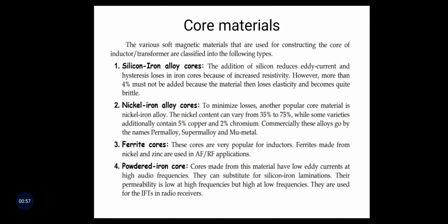First one, silicon iron alloy cores. The addition of silicon reduces eddy current and hysteresis losses in the iron core because of increased resistivity.